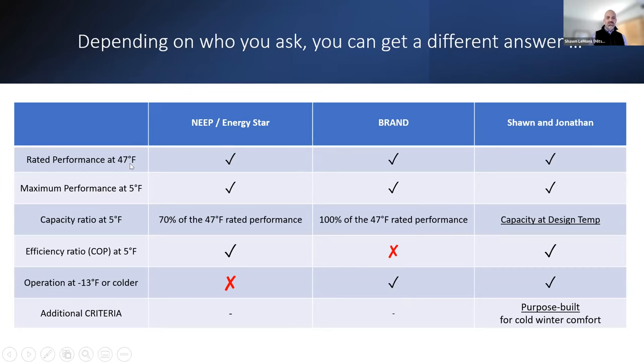Yeah, we agree that performance at 47, 13, and 5 are numbers that need to be looked at. But I underlined capacity at design temperature, and I think that's a really key piece. So rather than just looking at the capacity ratio, which is a tested metric that you're going to see in cold climate equipment selection, it's really important to work with skilled HVAC designers or professionals to look at the capacity of the system at that design temperature. Is it going to do the job, deliver the heat to meet the heating load for the house, specifically for comfort? And a key piece there is looking at equipment that is purpose-built for cold winter comfort, right?